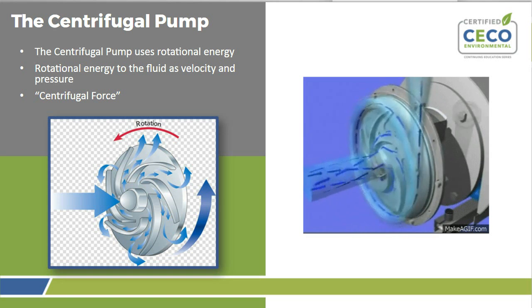That periphery is usually what we call a volute, and it's basically a diffuser that will raise the pressure of the fluid as it rotates around the casing of the pump. Then, of course, it is expelled out to do whatever purpose the pump is meant to do, whether it's just to move fluid from one spot to another, to move it through a process, what have you.